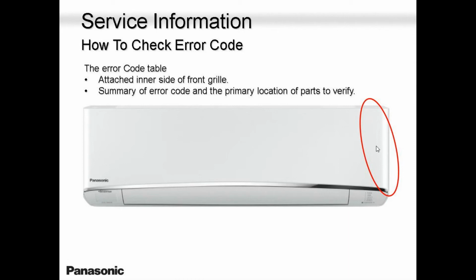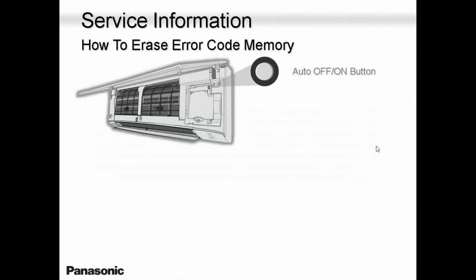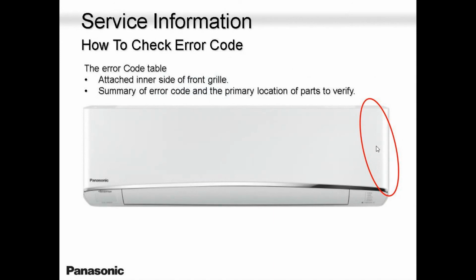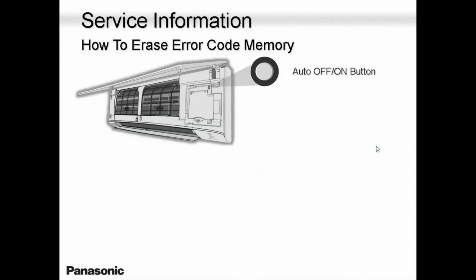And when the error code, for example, is H11, it will blink. It will beep at H11. And when it beeps at H11, you will look on your remote controller. And if it does not blink at H11, maybe let's say it beeps at H32. If you keep scrolling, when it gets to H32, the indoor unit is going to beep. Look at your remote controller and see H32. Then, just to be sure, go through all the codes and come back at H32, because our indoor unit, no matter which model, will only store one error code. And that error code is the current code.